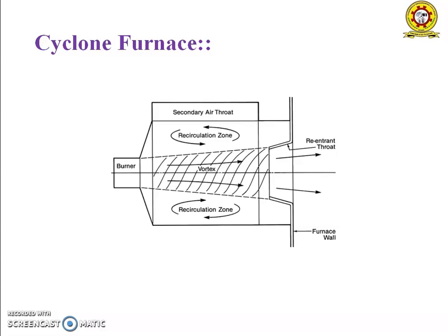The cyclone burner consists of a horizontal cylinder of about 3 meters diameter and 4 meters long. The cylindrical wall is water cooled, while the inside surface is lined with chrome ore. The horizontal axis of the burner is slightly inclined towards the boiler. The coal used in the cyclone burner is crushed to about 6 mm size.